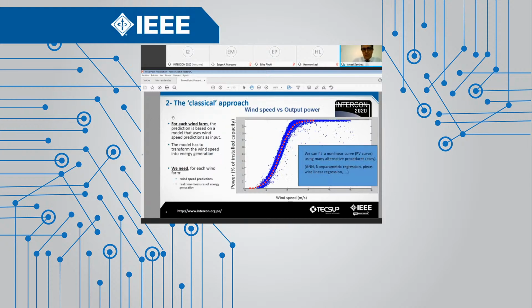How do they build the wind power prediction for each wind farm? There are many methods, but basically it can be explained with this picture. We have here in the x-axis the wind speed. So for efficient wind power prediction, you need the information of the wind speed. You need good wind speed predictions, hourly and updated as much as possible. And in the y-axis you have the actual production. Actual production is easy to have because utilities are paid for that information, so it's information of very high quality.